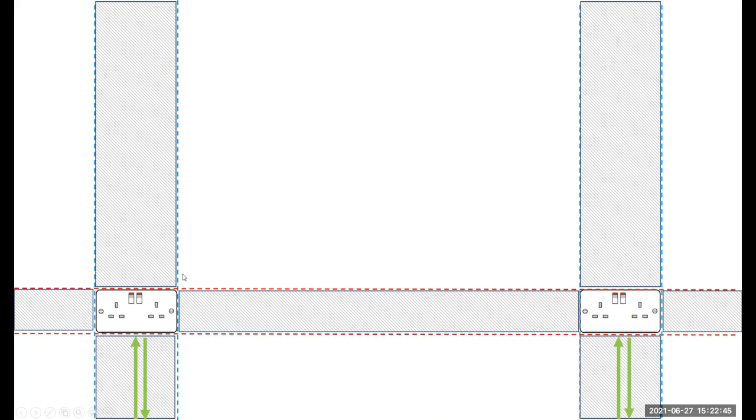It's also a good idea to keep your circuits the shortest possible so that you get the best readings and the lowest value, so that your overcurrent protective device is going to trip out the quickest. Buried cables should be kept to a minimum and vertical, not horizontal, thus minimizing impact on the wall structurally. So yes, you can go horizontally, but again, vertically is best.